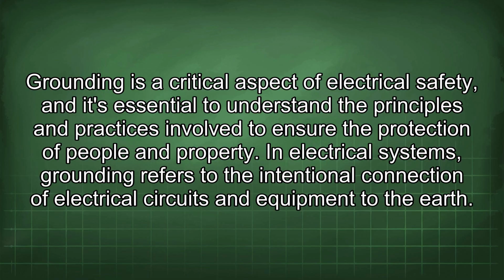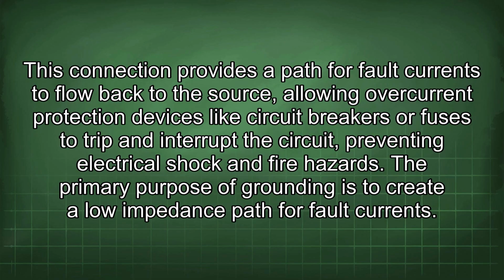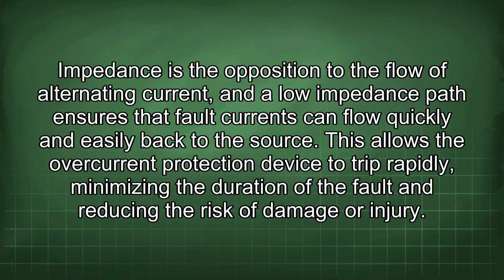In electrical systems, grounding refers to the intentional connection of electrical circuits and equipment to the earth. This connection provides a path for fault currents to flow back to the source, allowing overcurrent protection devices like circuit breakers or fuses to trip and interrupt the circuit, preventing electrical shock and fire hazards. The primary purpose of grounding is to create a low impedance path for fault currents. Impedance is the opposition to the flow of alternating current, and a low impedance path ensures that fault currents can flow quickly and easily back to the source.